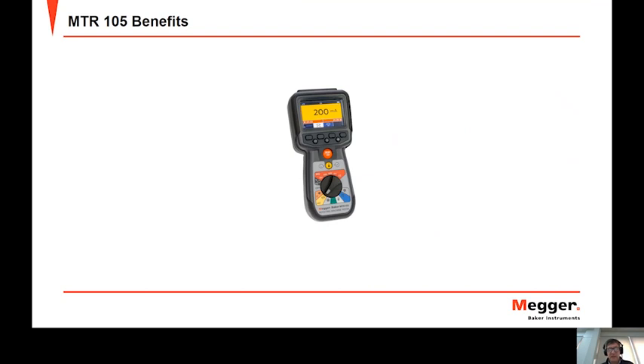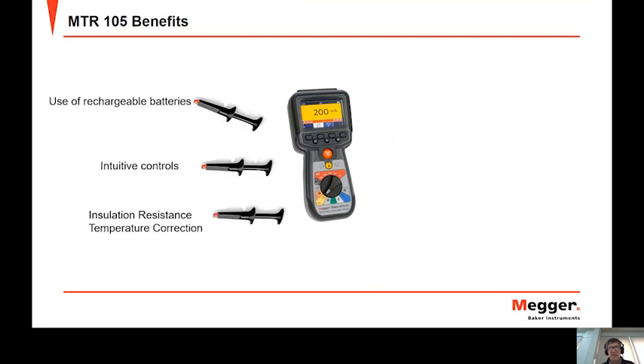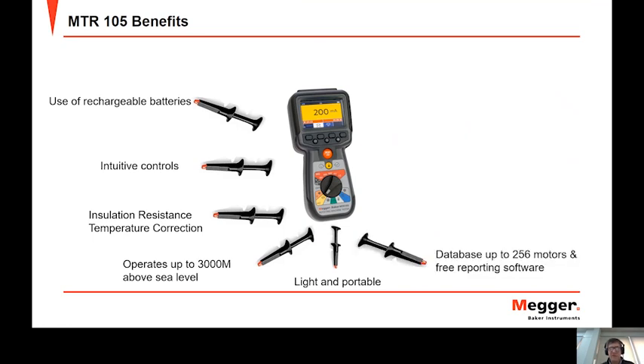So some of the benefits include the small form factor. It's light and very easy to carry. We have the possibility to use rechargeable batteries or just AAs otherwise. We have intuitive controls and graphics, so it's very easy to use and to learn how to use. The unit provides insulation resistance values which are temperature corrected, which is very important and we'll talk about later. It can even operate up to 3,000 meters above sea level if that's important to you. We've already said it's light and portable, and we have the ability to store up to 256 records or motors. All of the tests go into that record, and then it can be transferred to the software that I mentioned earlier.